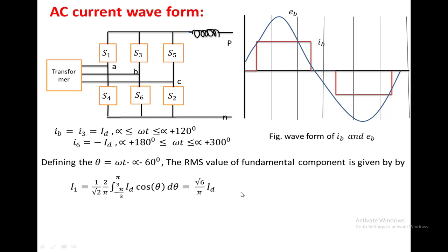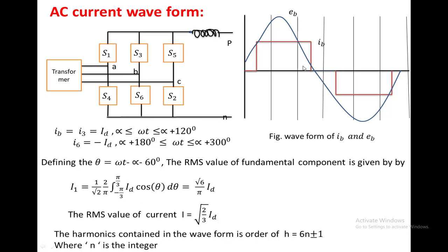The RMS value of the phase current from this waveform is I equal to root(2/3) times Id. From Fourier analysis, this current contains harmonics of order 6n plus or minus 1: for n equal to 1 we get the 5th and 7th harmonics; for n equal to 2 we get the 11th and 13th harmonics, and so on. These harmonics flow through the transformer.